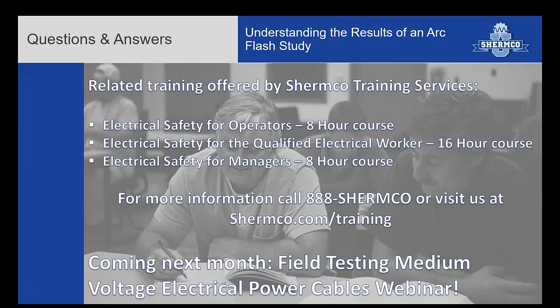I mean, if we just go back to NFPA 70E and Article 110 where they talk about training, basically what it really comes down to is the qualified person with familiarity with the gear, understanding of its operation, et cetera, and then using that information for the risk assessments, conditions of the day, et cetera. Now, you can go into your hierarchy of controls where obviously at the very top, elimination, shut down, don't do the task live if you can avoid it. From there, you can go into engineering controls or substitution methods like, again, getting length, using poles or something would be a substitution method.